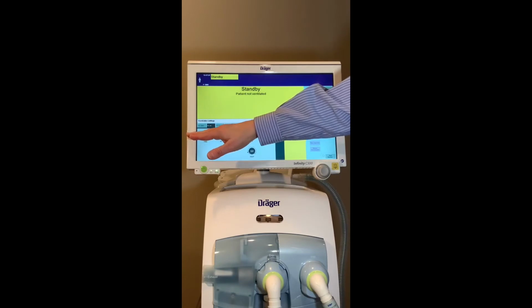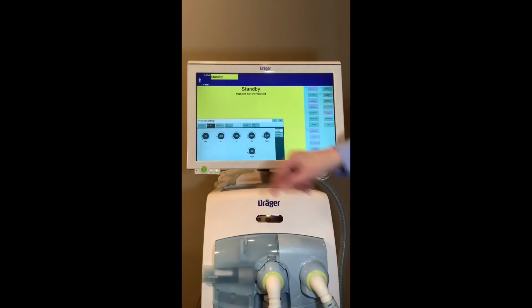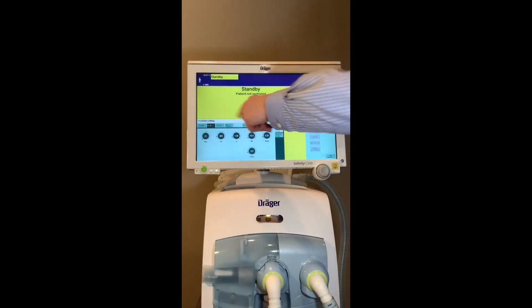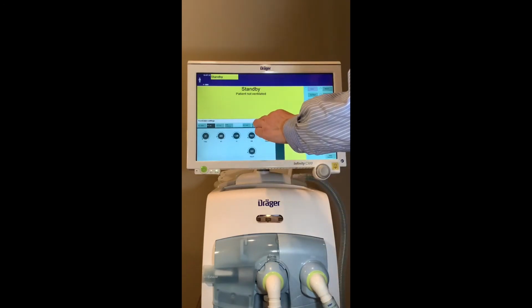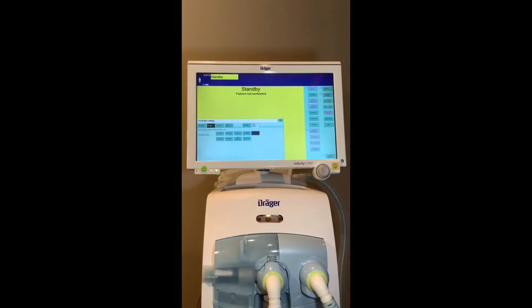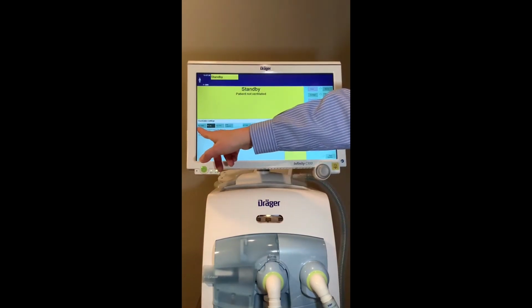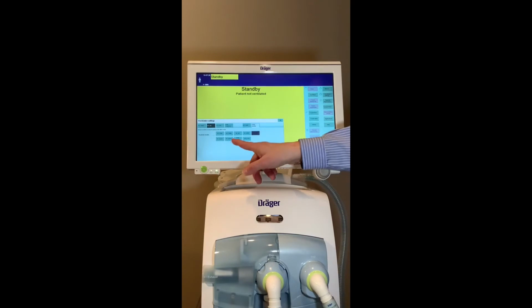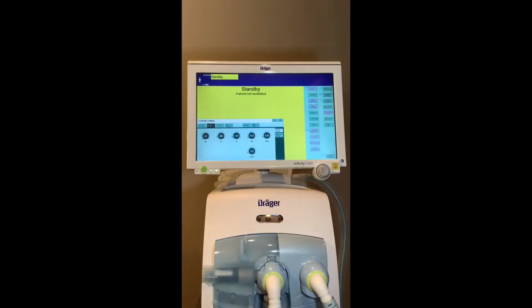Your modes of ventilation displayed in the tabs across the top are going to be the modes that are most often used, but by pressing the Other Modes button, it will show you all the modes that the ventilator has. The nomenclature on the V500 includes a prefix for every mode of ventilation: PC to indicate pressure control, VC to indicate volume control, and SPN to indicate spontaneous breathing.